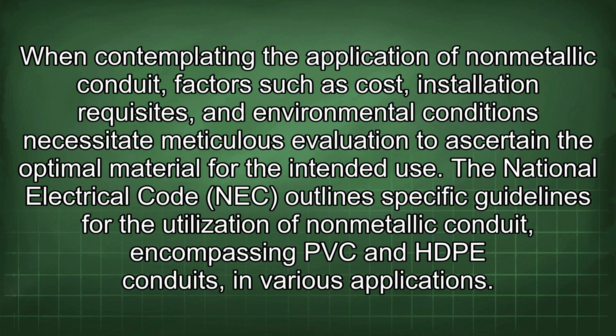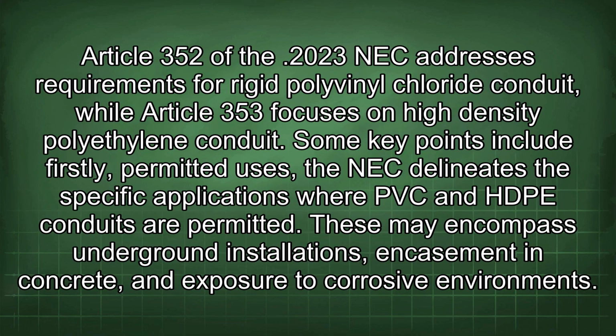The National Electrical Code (NEC) outlines specific guidelines for the utilization of nonmetallic conduit, encompassing PVC and HDPE conduits, in various applications. Article 352 of the 2023 NEC addresses requirements for rigid polyvinyl chloride conduit, while Article 353 focuses on high-density polyethylene conduit. Some key points include: firstly, permitted uses. The NEC delineates the specific applications where PVC and HDPE conduits are permitted.